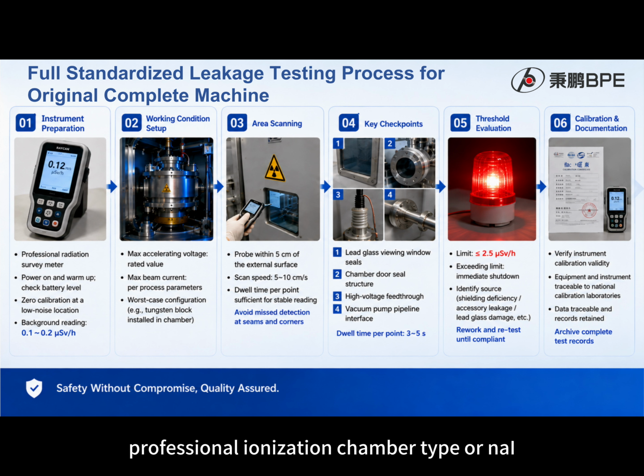Four critical leakage points are carefully inspected: the lead glass and door frame joint, chamber door O-ring seal, electron gun high-voltage cable flange, and vacuum pump interface. Each point is monitored for 3-5 seconds. If the dose rate approaches or exceeds 2.5 μSv/h, the high-voltage supply is immediately shut down. After any repair, the complete test is repeated. Radiation survey meters must also be calibrated annually, and all test records are properly archived.